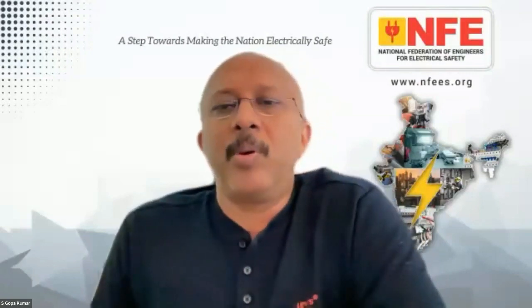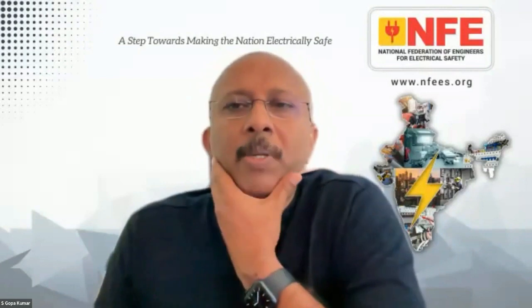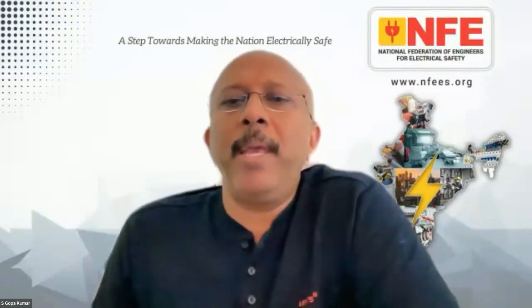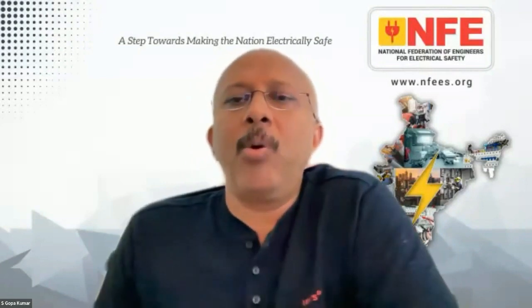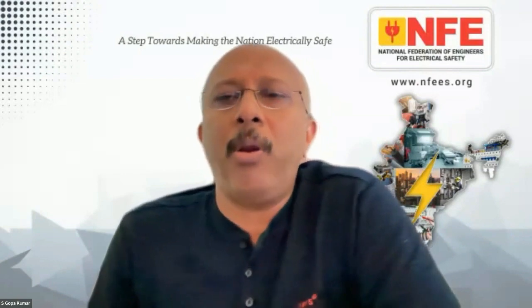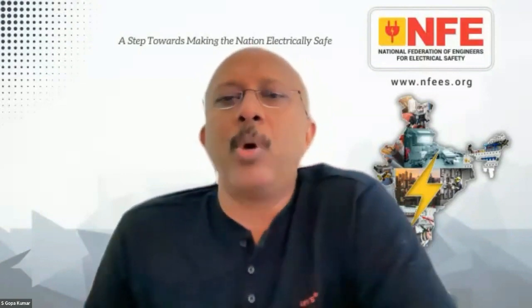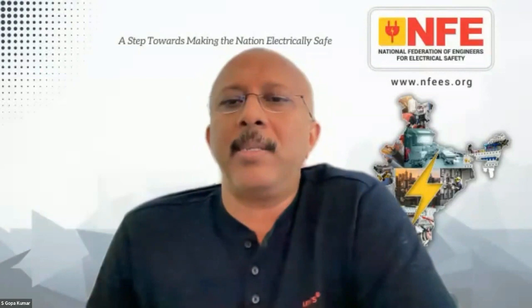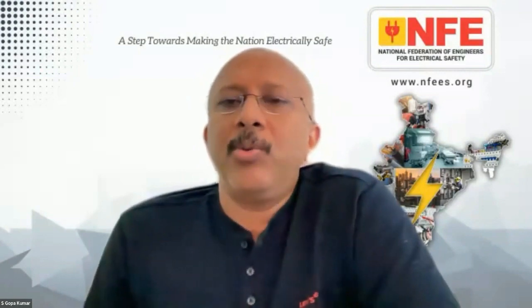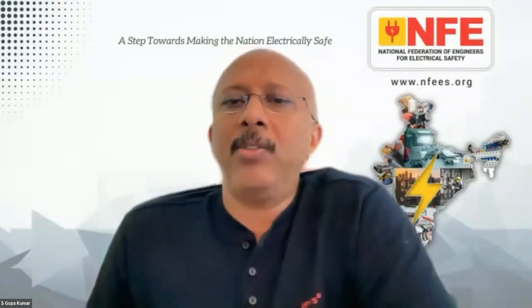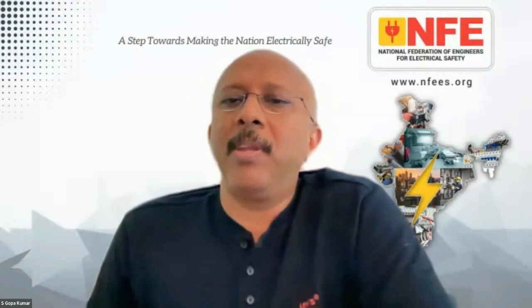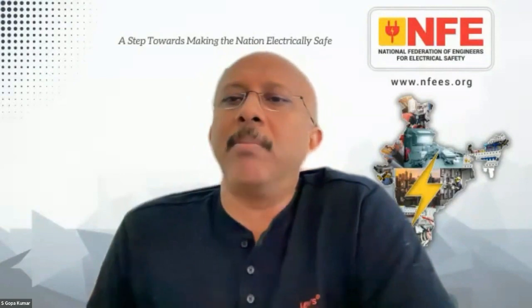So in simple conclusion, you must bond it, but you should not allow the whole fault current to flow through this route. That is what is necessary. So the next question from Mr. Sanjay Mulai: in case of a TNCS system, if the neutral is broken, then what is the protection to avoid overvoltage in the distribution system?